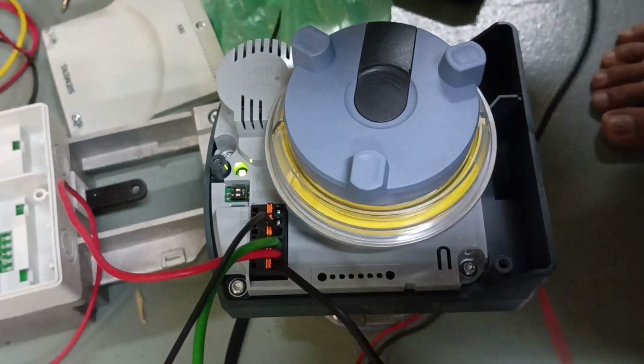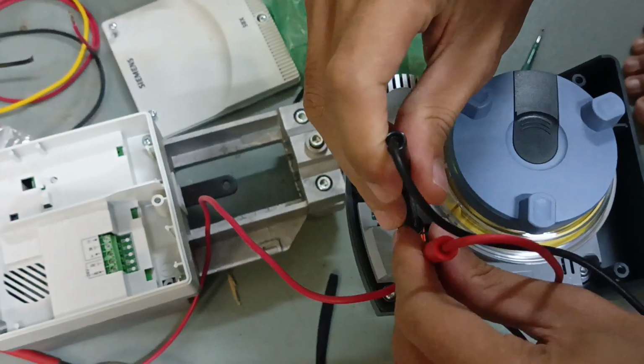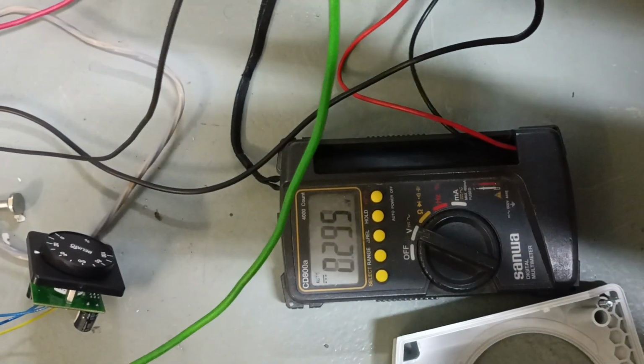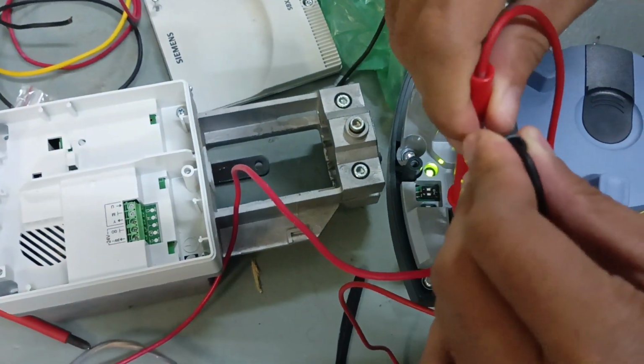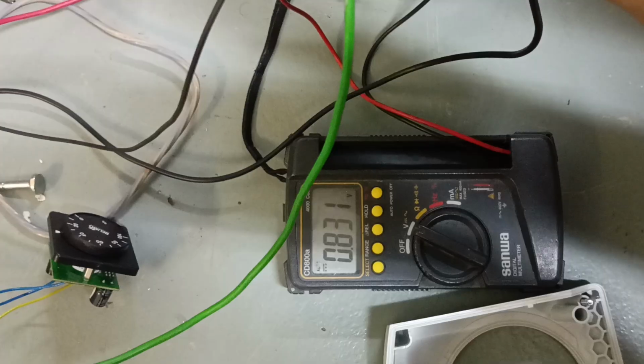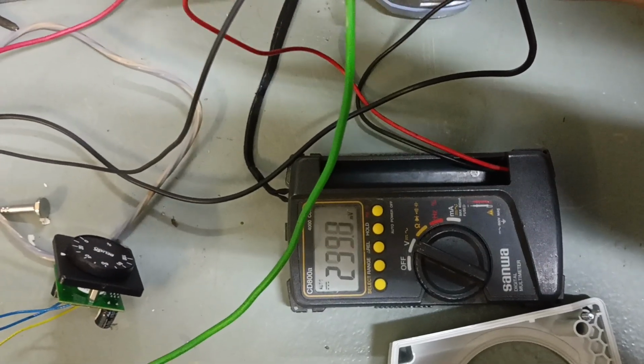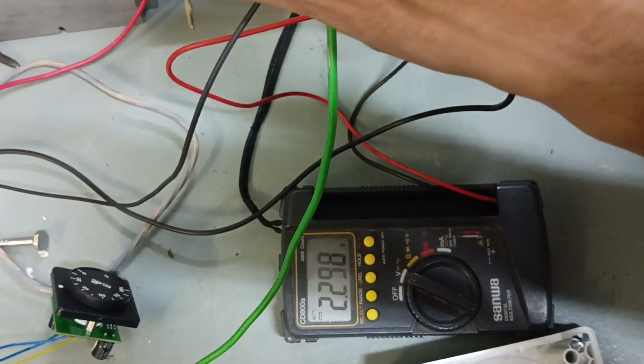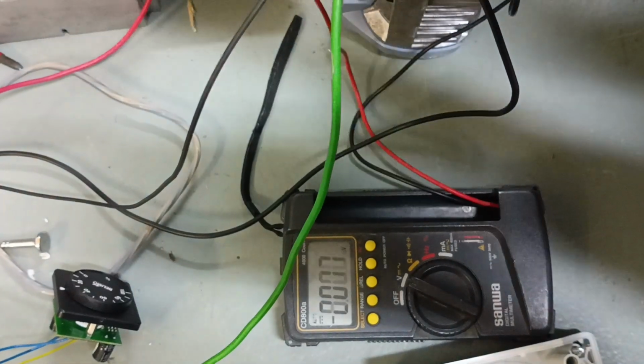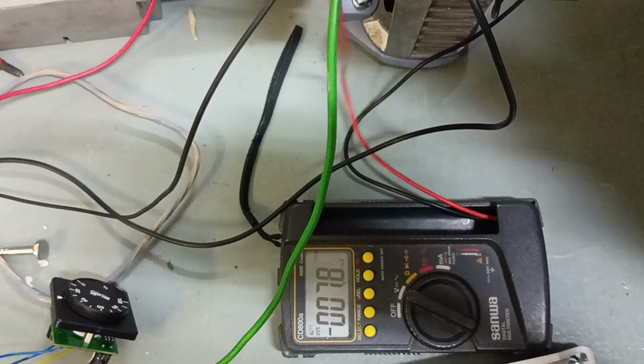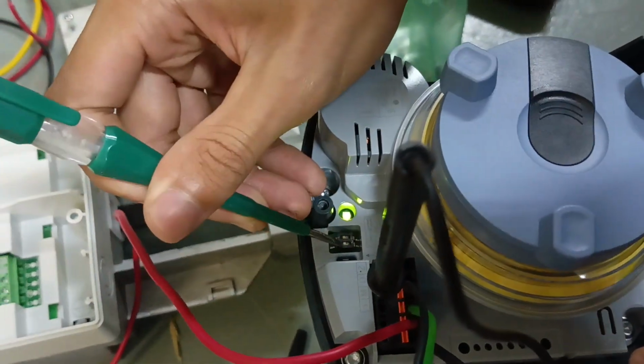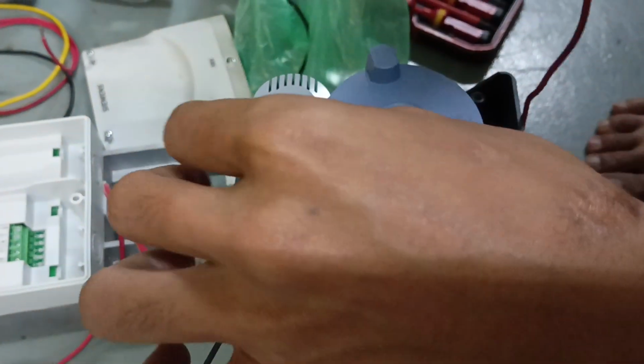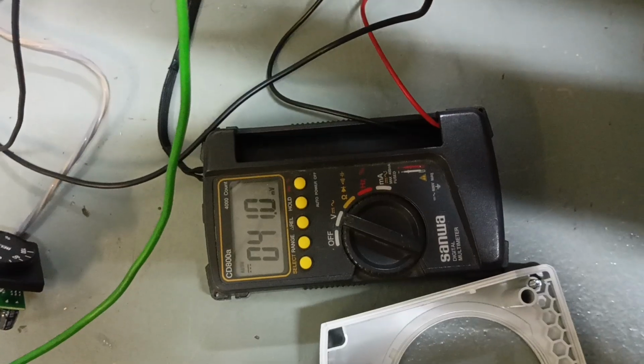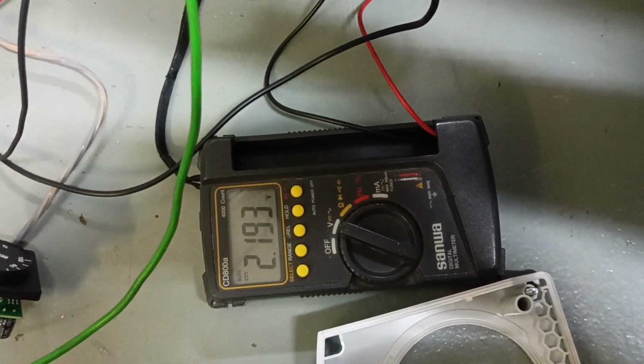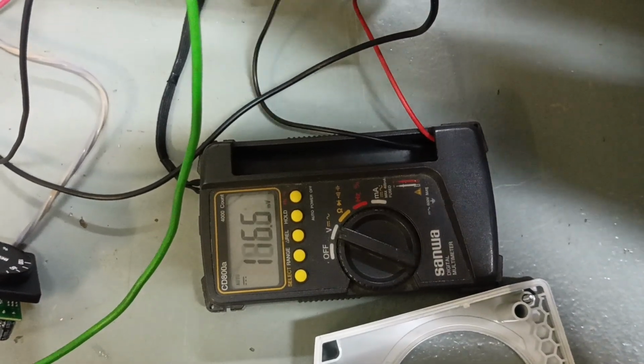For example, now the signal is 2 volt, but the feedback will be less, you see feedback 0.8. This is to make sure that when the valve opens a little, the pressure is not too high, so that's why this setting is used. If you want to change to linear, you just push number 2 to on and the actuator will open. In linear mode, for example, with a 2 volt signal, the feedback can also get 2 volt, so that's why it's called linear. So that's all the difference.